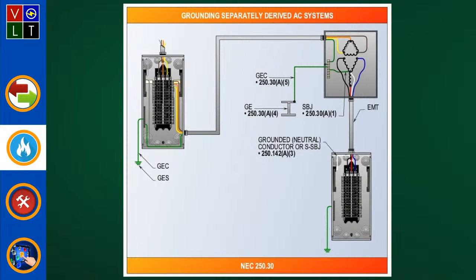What we're going to look at now is separately derived systems. This is just a basic illustration, and in our publication we explain that you have low voltage, high voltage feeders, sometimes installed like you'd see in a high rise building, where transformers are installed on each floor to reduce the voltage, say to 120/240 or 120/208 volts, for general lighting and receptacle loads in these large building applications.